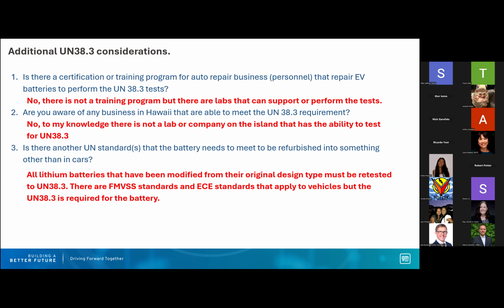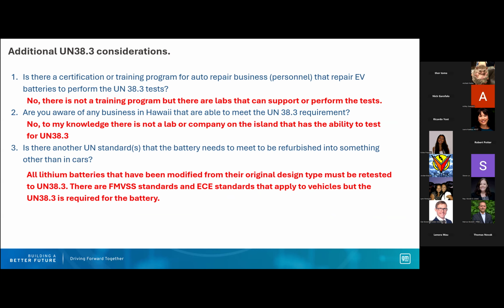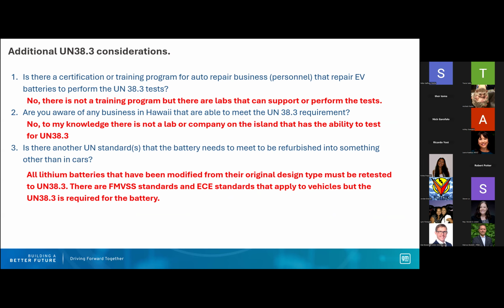Are you aware of any businesses in Hawaii able to meet UN 38.3? No, not to my knowledge—there isn't a lab on any island that does UN 38.3 testing. There are a few in the U.S., usually in the US or China, but typically either the OEM has built a lab with the capability to do the testing and certification, or you send it to a third-party lab. There are a couple of really good ones out there, like Intertek, that can perform the testing, along with numerous other labs certified under that standard. Now, if you go to a lab, they have to be certified to do that testing, and that's a process in and of itself.